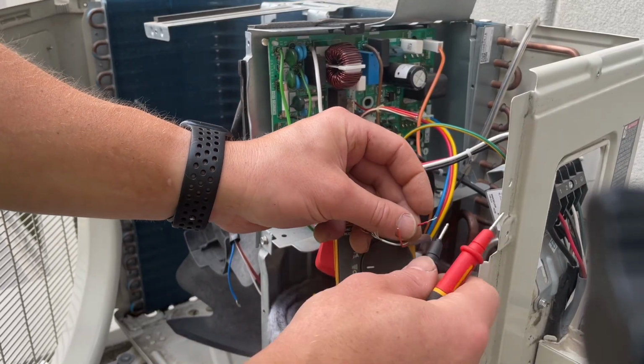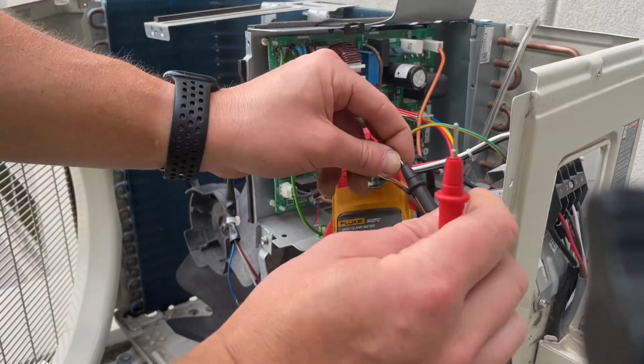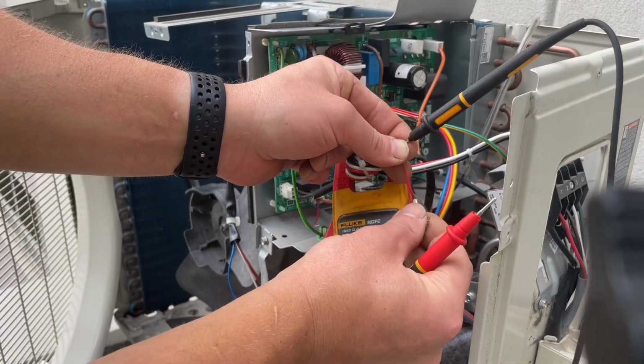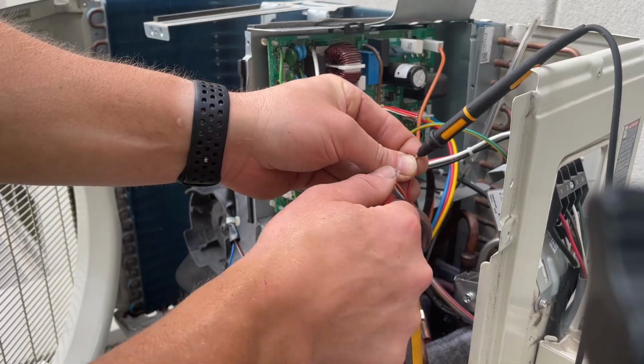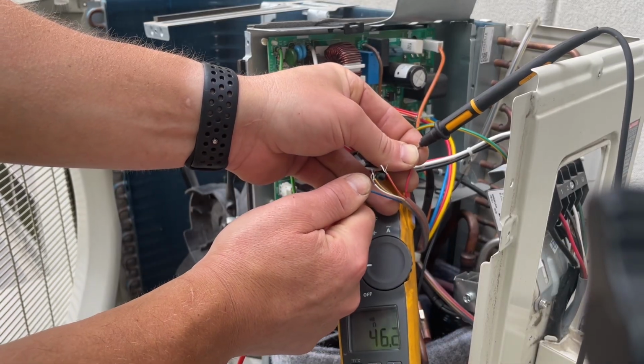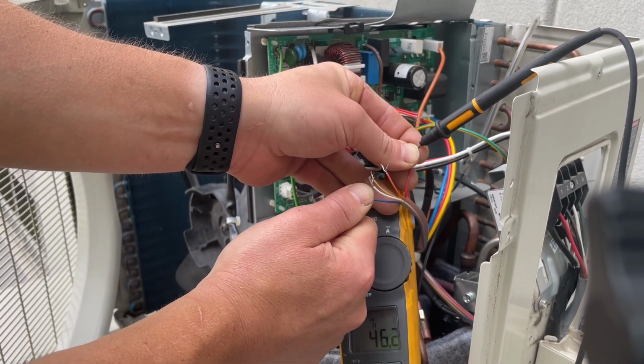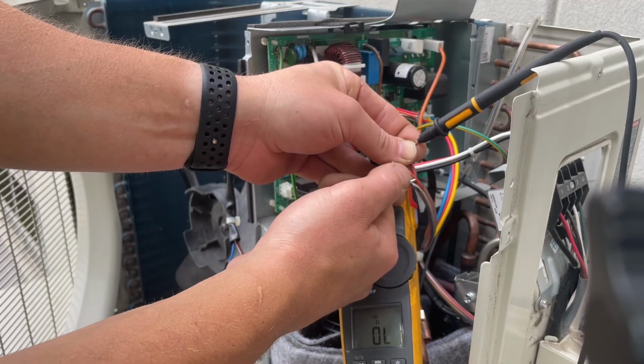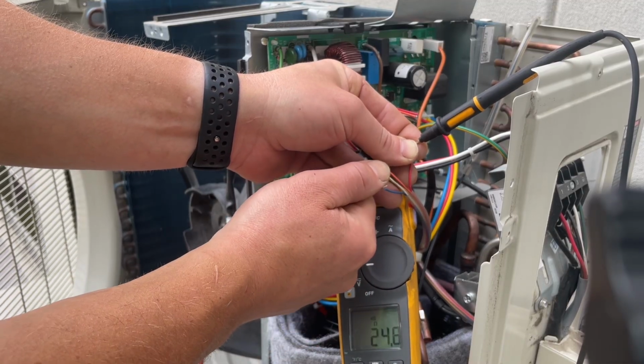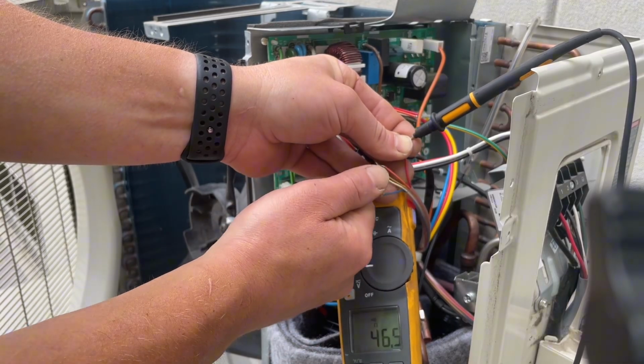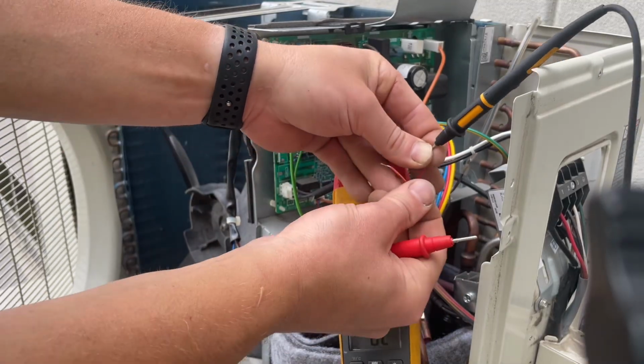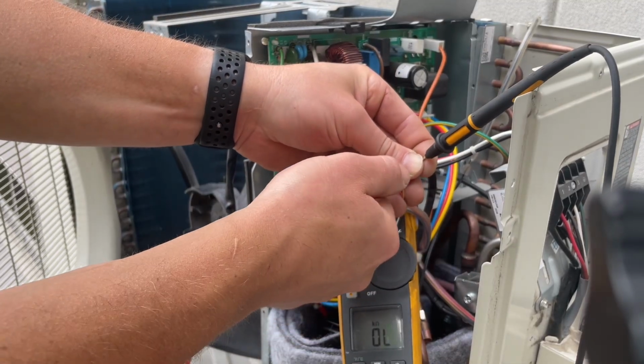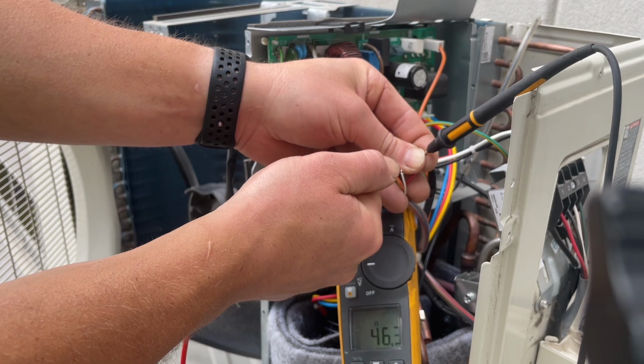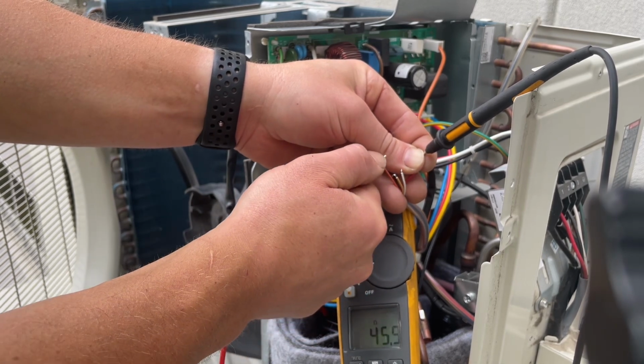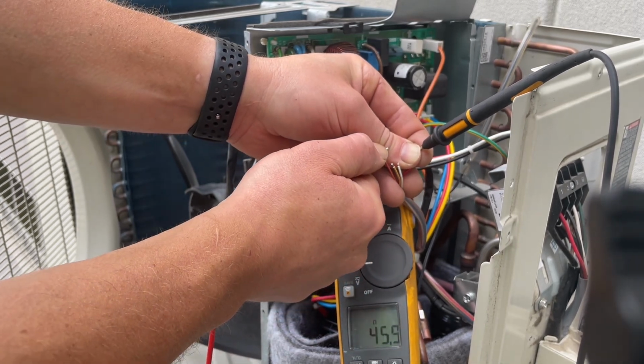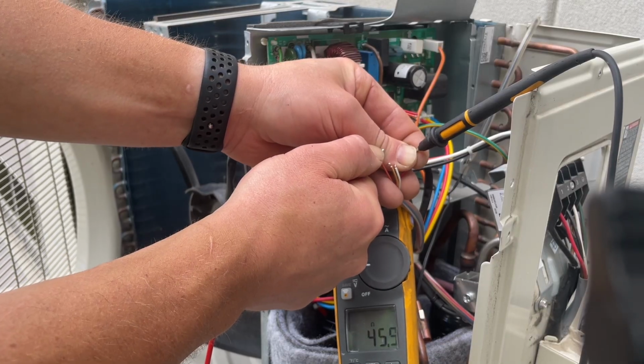Red is our common this time. So everything we're going to reference off our red lead. So every wire between our red terminal should be roughly between 40 and 50 ohms. That's how we're going to verify that our EEV is okay. 46, it's good. Let me separate these a little bit better. 46 ohms, and then finally our orange, 45.9 ohms. So we know our electronic expansion valve is fine.